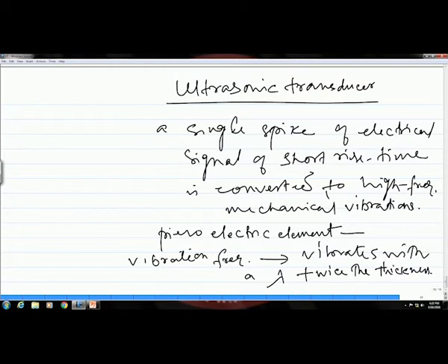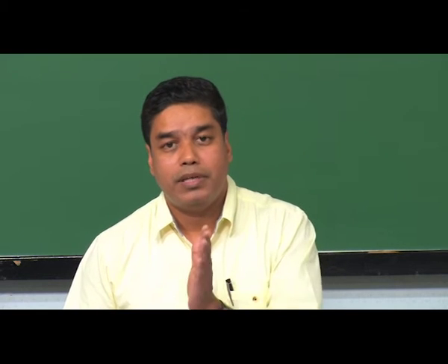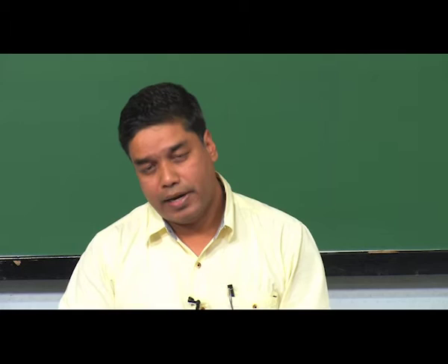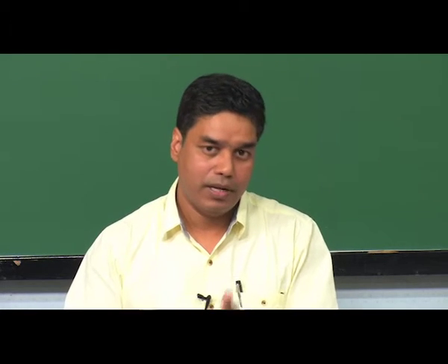Okay. So, let us see how is the construction for these ultrasonic transducers. But before that, let us talk about what is the material of this piezoelectric element, and what are those parameters which control the transmitting and the receiving ability of this element or the transducer. So, the most commonly known piezoelectric material, as you might all know, is quartz.